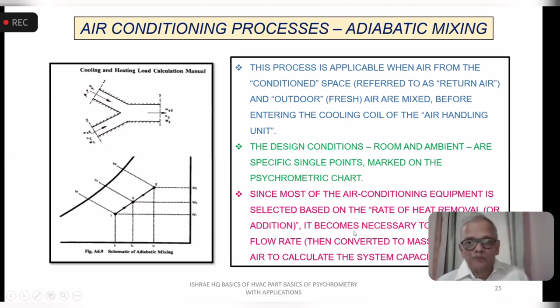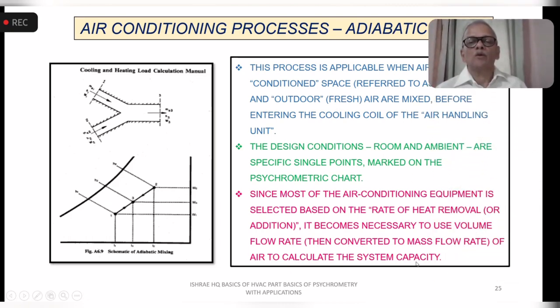Now, since most of the air conditioning equipment is selected based on the rate of heat removal or rate of heat addition, it becomes necessary to use the volume flow rate and then convert it to mass flow rate to calculate the system capacity. So you have the air flow rates. You will hear the word CFM most of the time whenever you are having a discussion with AC engineers. It could be liters per second or CMH, meter cube per hour, but that's basically the flow rate. And then you have to use the specific volume to convert it to the mass flow rate, because all your heat equations are dependent on the mass flow rates.